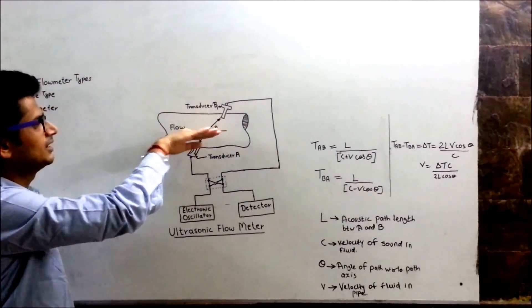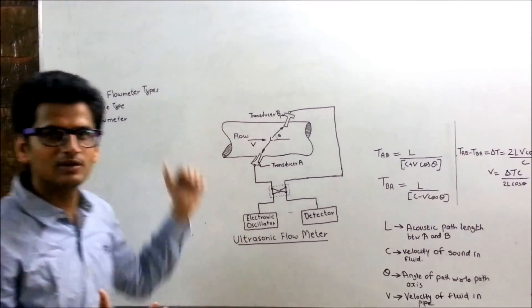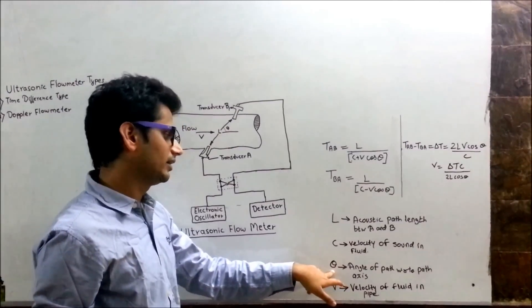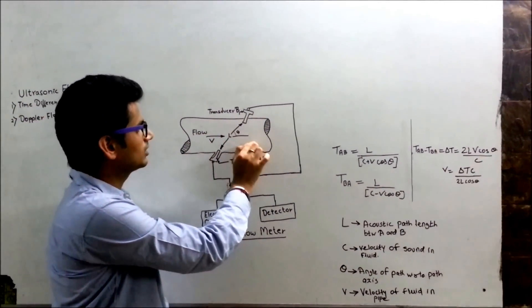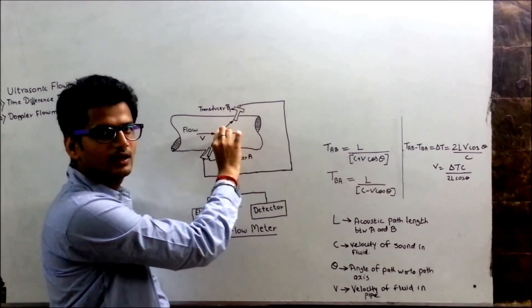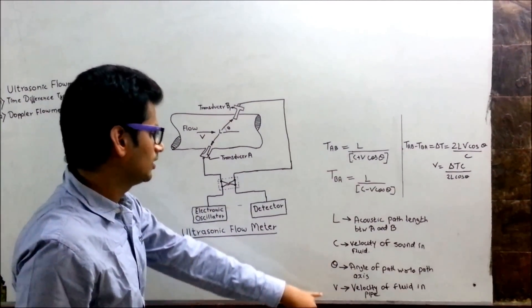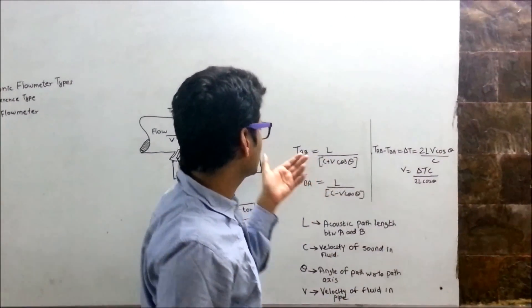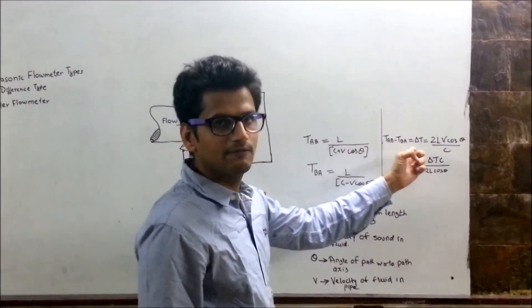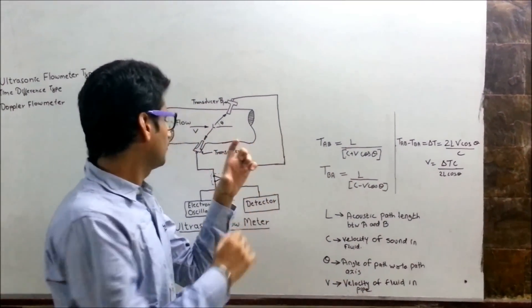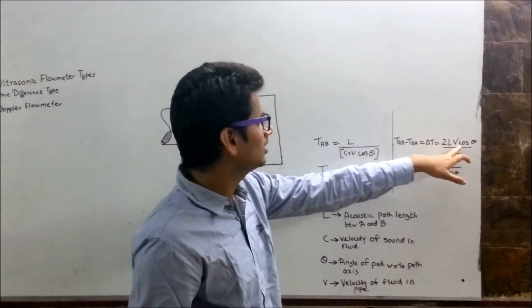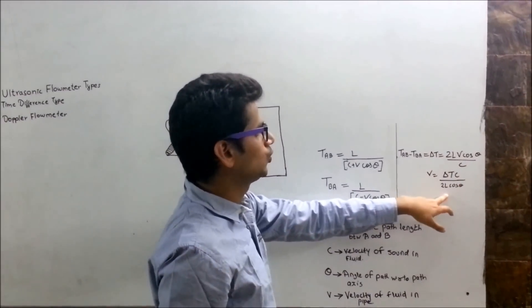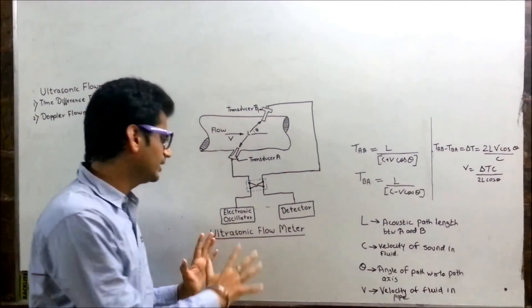And C is the velocity of sound. Because our fluid is flowing from here, there are various sounds produced, that is why we have to determine its velocity. Then there is an angle of theta. Now, we have TAB and TBA, if we take the difference between the fluid, we will get the total measurement of the fluid, which is 2L V cos theta upon C. But if we take V to this side, we will get delta T C upon 2L cos theta. So this is how basically ultrasonic flow meter works.